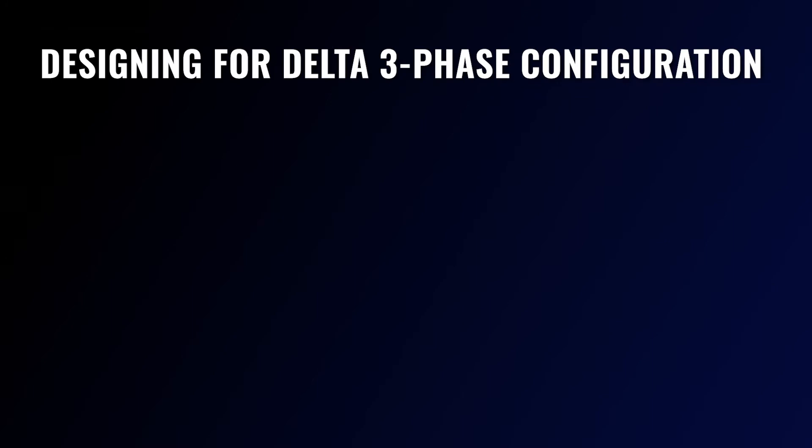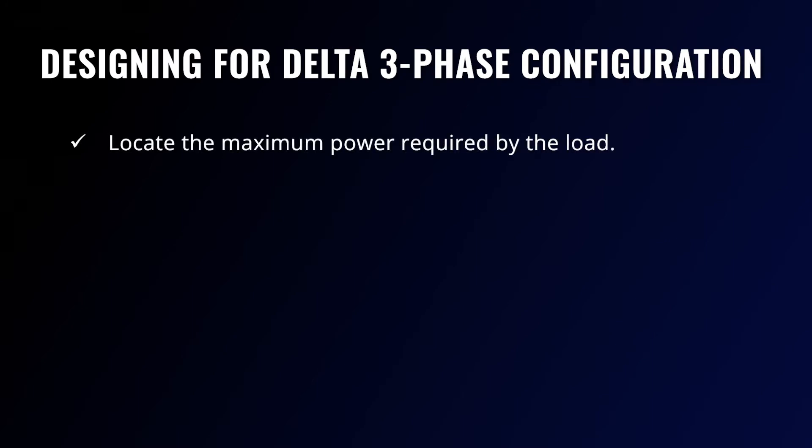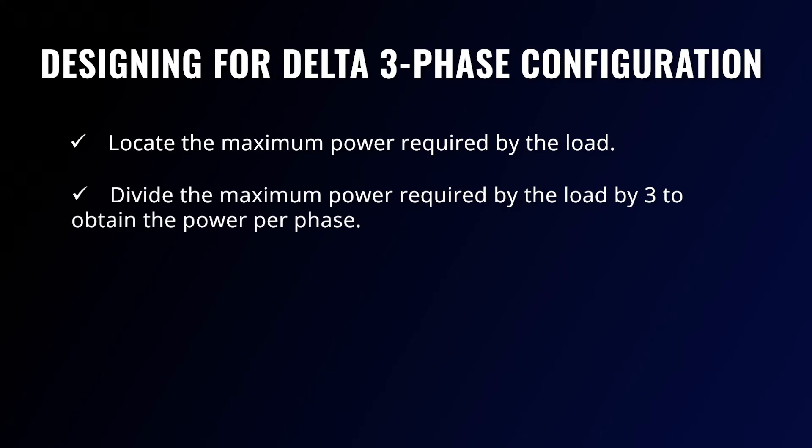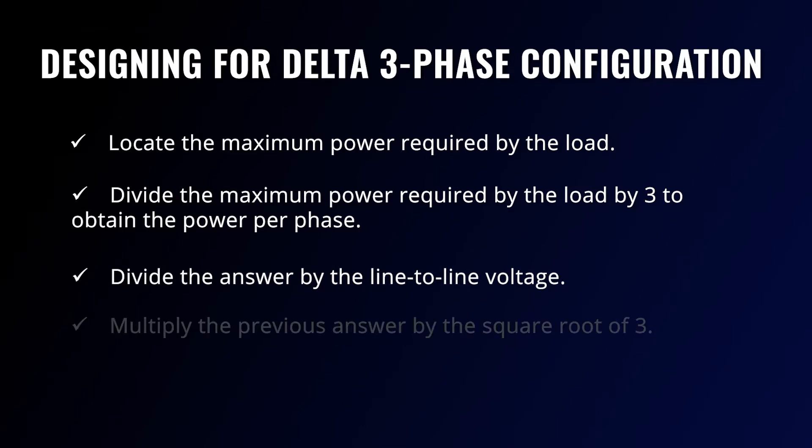Because of the absence of the neutral wire, capacitors used in delta three-phase EMI filters have to be rated for the line-to-line voltage, which can increase the size, weight, and cost. To design for delta three-phase EMI filters, you must locate the maximum power required by the load, divide the maximum power required by the load by three to obtain the power per phase, divide the answer by the line-to-line voltage, and multiply the previous answer by the square root of three. Delta configurations can typically be designed to handle higher currents more frequently. They are usually set up for heavy-duty applications and are preferable for power generation and transmission. It is also considered a simpler configuration.